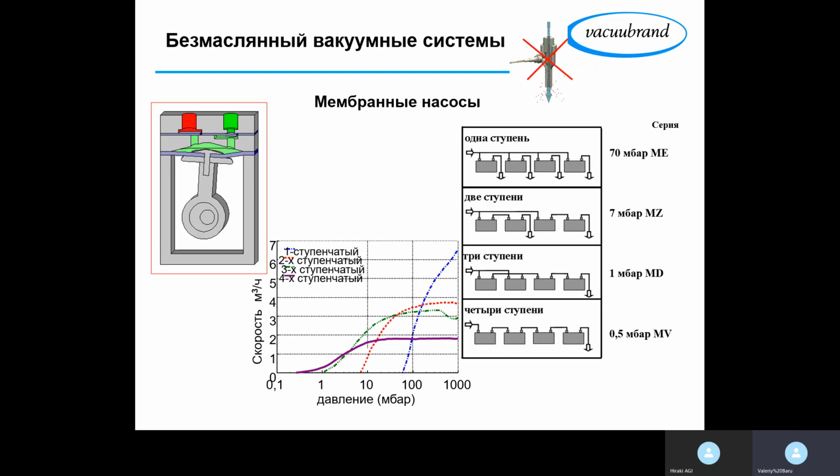This kind of system exists as well, by the way, but they have another type of leaks. Not the leaks from the atmosphere, but the leaks from the surface of the materials that this chamber is manufactured of. Another type of very crazy leaks, but this is not something I want to kill your brains with, because this is high vacuum applications, and this is not something that you are dealing with in your daily business.